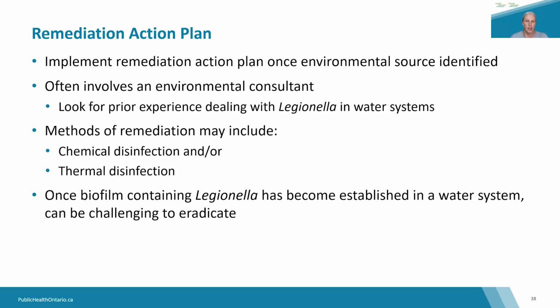So it can be very challenging to pinpoint the source of illness. However, once the environmental source of Legionella has been identified, the next step for the facility or water system operator is to develop and implement a remediation action plan. And a remediation action plan should include disinfection procedures that are effective against Legionella, target the risks or sources associated with the case, and minimize the adverse impact on the equipment and building occupants. So it's best to consult with an expert, as a tailored approach is often necessary. The most common methods of remediating contaminated water systems are chemical disinfection, thermal disinfection, or a combination of both. And I'll reiterate that once Legionella within biofilm has become established in a water system, it can be very difficult to eradicate. Next slide, please.